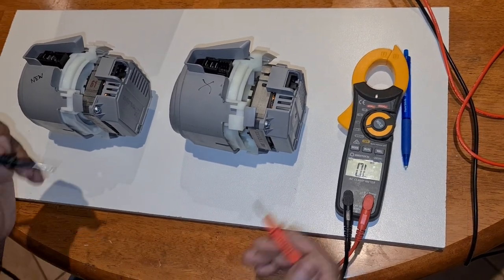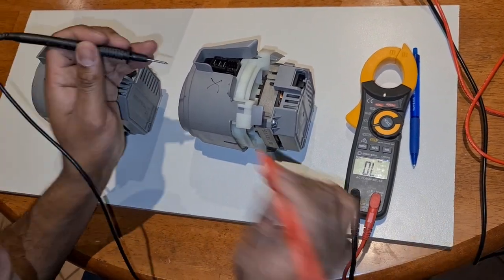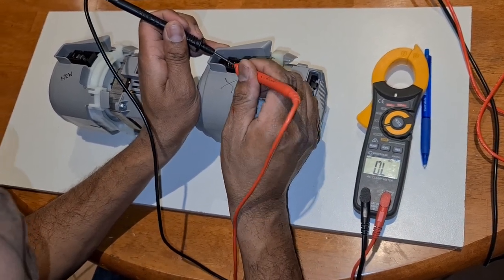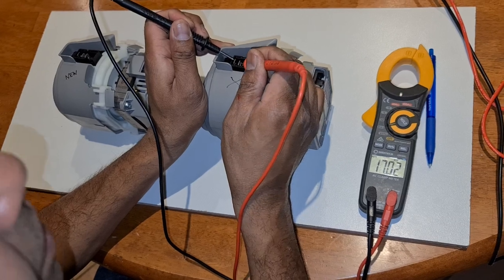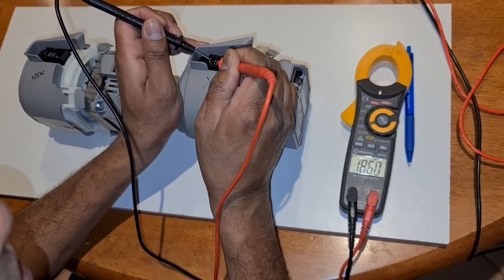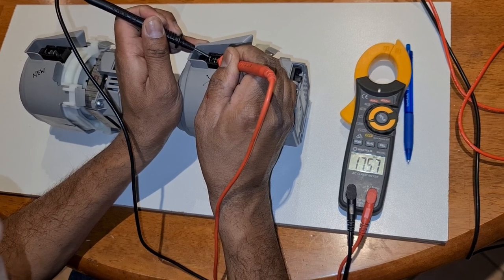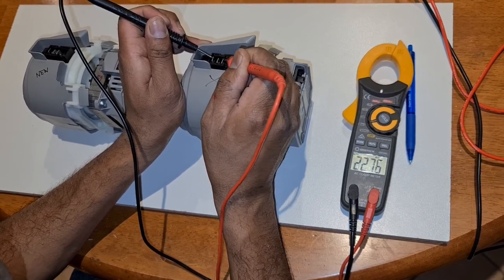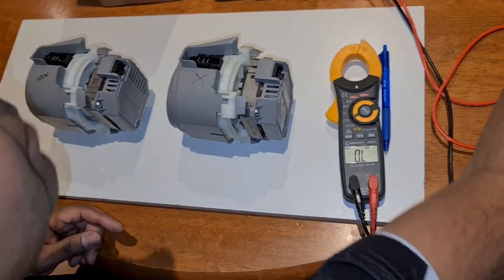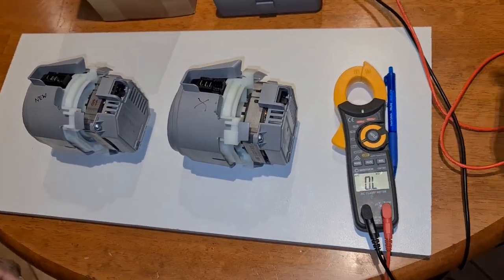So sometimes people do a megger test with a multimeter going from earth to the live terminal. And they take a reading and say, you know what, that's okay. 17 and a half meg, it should be fine. But this bad one is actually tripping the circuit breaker.